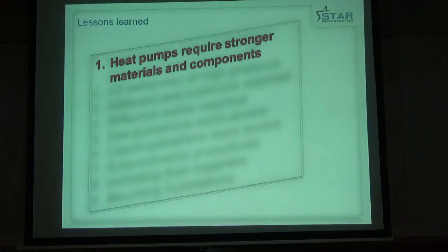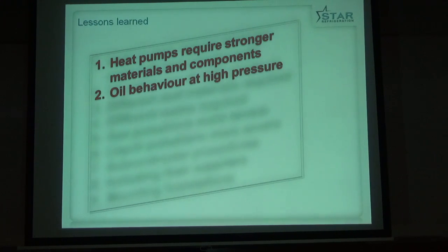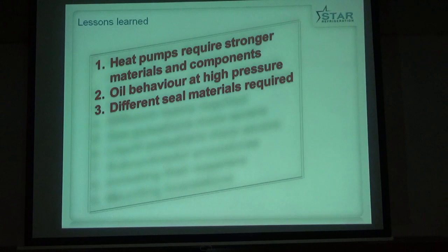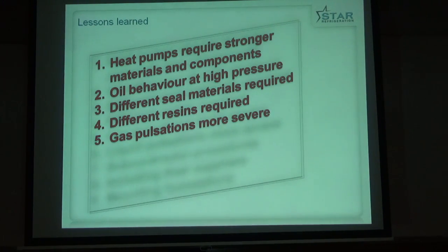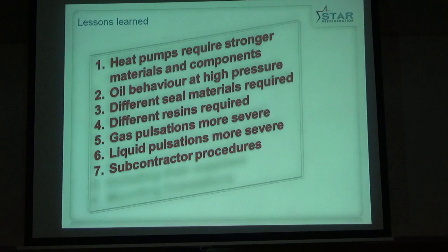So the lessons we learned: we need stronger materials and components. The oil doesn't behave the same way when it's at high pressure. We need different seal materials, different resins in the oil separator. The gas pulsations are much more severe than they would be. Liquid pulsations also more severe. The reason we had the tube failure is because our subcontractor who manufactured the heat exchanger had not followed a robust enough quality procedure, so he had used this dubious material.